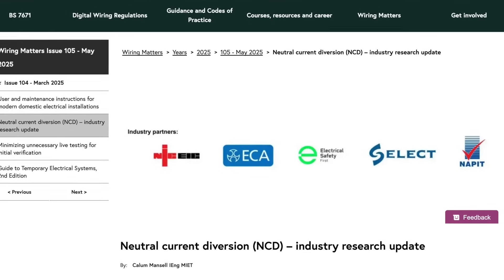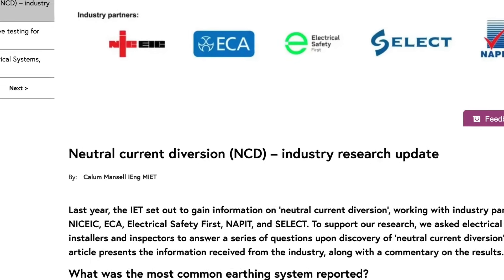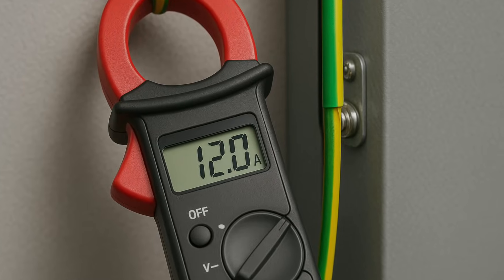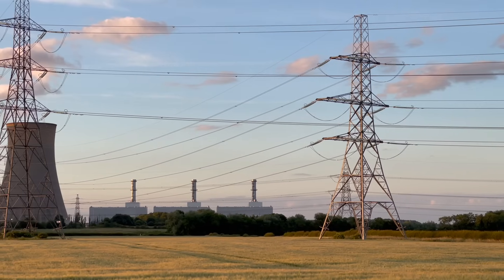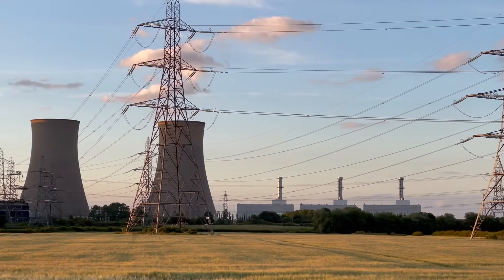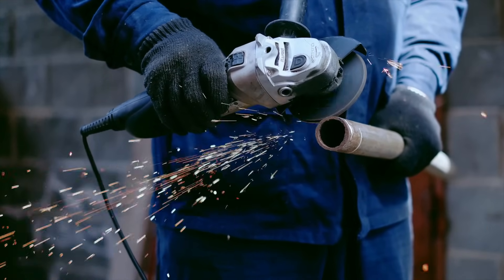The author of the wiring regulations is warning the trade this week about the high currents that can be found in a neutral current diversion. A survey by the IET has revealed that currents can reach up to 67 amperes during the fault. The average current measured during the incidents compiled by the survey was 12 amps. One electrician reported no current at first, but when a neighbour switched something on — boom — 43 amps suddenly appeared. It's all down to network impedance and load distribution. In another case, a gas installer investigating sparks on the gas installation pipework when a nut was undone recorded the presence of almost 4 amps.